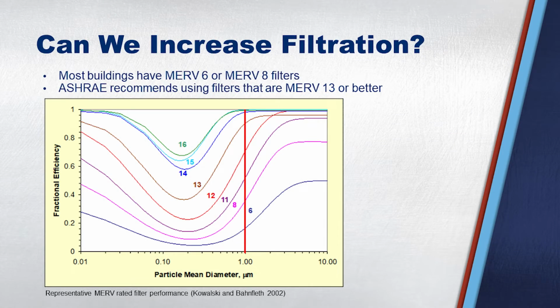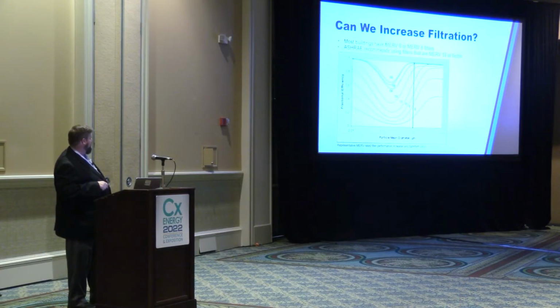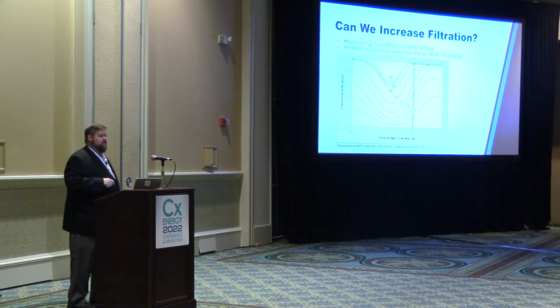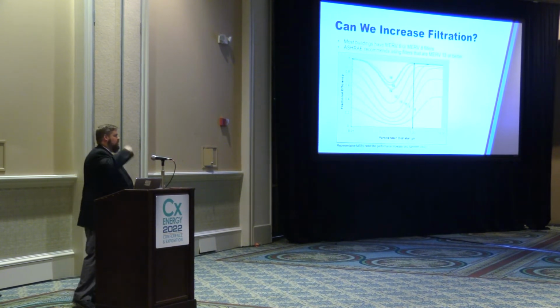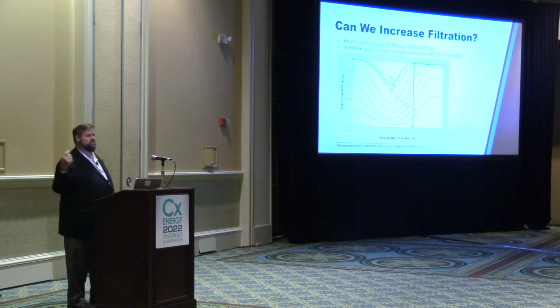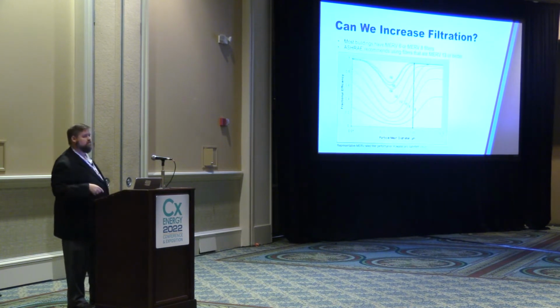Moving to filtration, it's why ASHRAE came out and said MERV 13 is preferred, typical. If you look at this virus and say, hey, at 1 micron, a MERV 8 filter is in the 30% range. A MERV 13 filter is in the 90% range. That's a huge improvement in terms of removing particles. Well, the virus floats around on particles, so if I remove more particles, then I'm removing more virus. But there's pressure drop and other things that are associated with this.